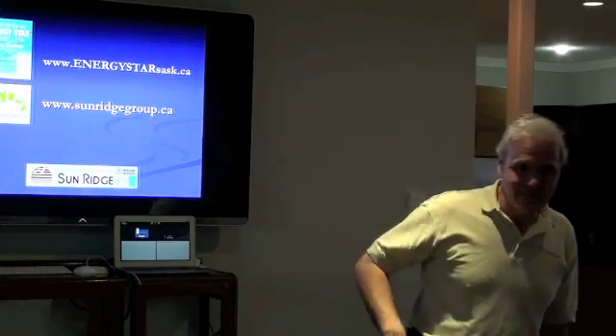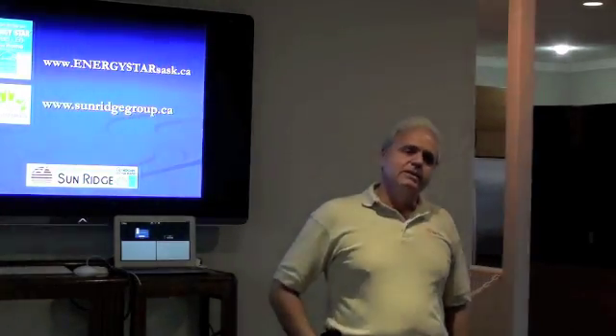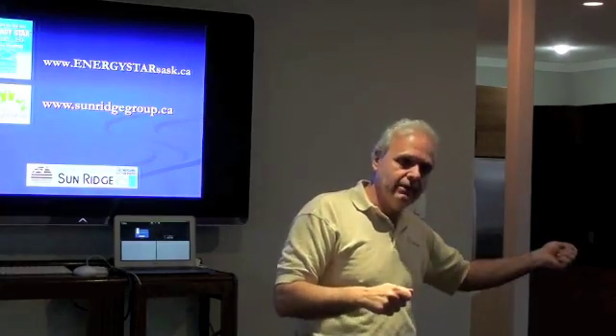So at one point you mentioned that retrofitting with HRV is difficult. The reason for that is that many times, most existing houses have exhaust-only ventilation systems. By that I mean we have a bathroom fan with an on-off switch and it just vents directly outside all 3 of the bathrooms or whatever there's in the house. The kitchen usually will have an exhausting range hood that goes directly outside.